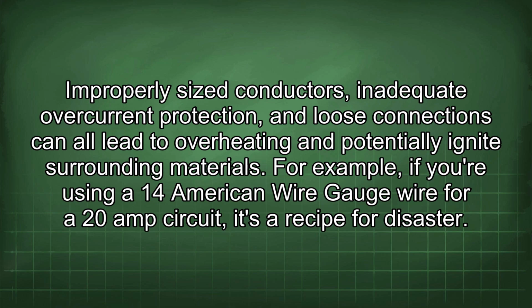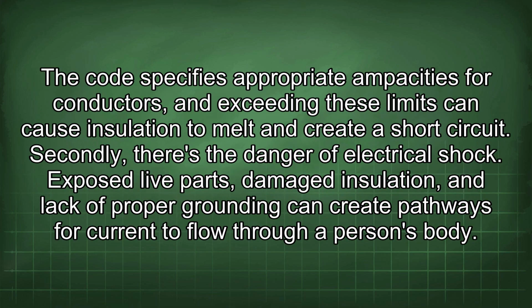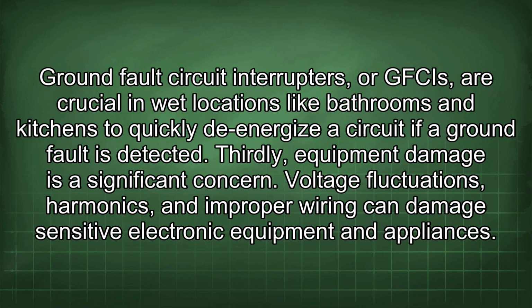For example, if you're using a 14 American wire gauge wire for a 20 amp circuit, it's a recipe for disaster. The code specifies appropriate ampacities for conductors, and exceeding these limits can cause insulation to melt and create a short circuit. Secondly, there's the danger of electrical shock. Exposed live parts, damaged insulation, and lack of proper grounding can create pathways for current to flow through a person's body. Ground fault circuit interrupters, or GFCIs, are crucial in wet locations like bathrooms and kitchens to quickly de-energize a circuit if a ground fault is detected.